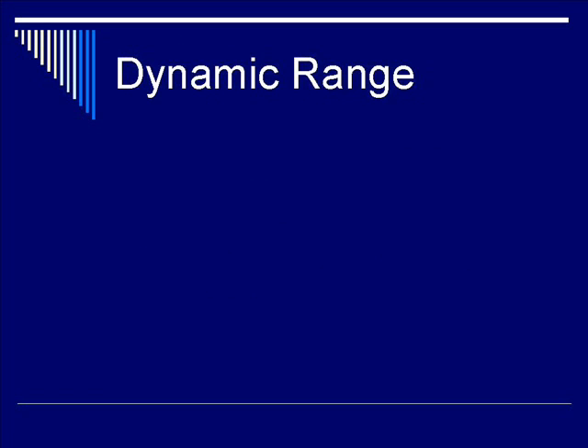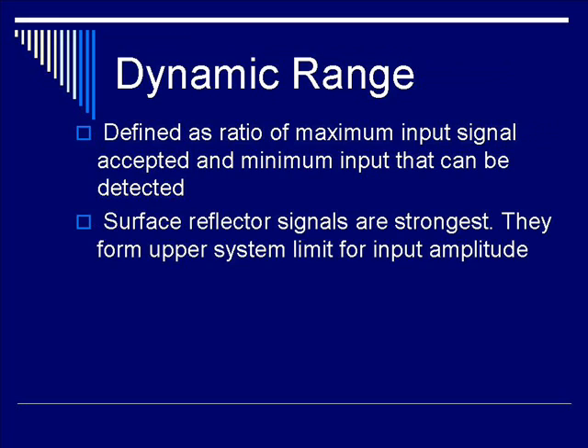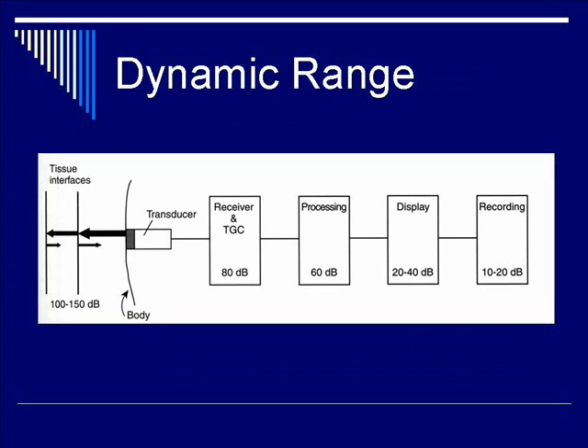The definition of dynamic range is the ratio of the maximum input signal over the minimum input signal that can be detected. Surface reflectors typically give out very strong signals, forming the upper limit for input amplitude. On the other hand, deep reflectors give out very weak signals — sometimes requiring amplification up to 1,000 times just to be detected — and are compromised by noise from the transmission cable as well as the low noise amplifier. In terms of system components, the receiver has a very high dynamic range up to 80 dB, whereas displays and recorders typically have a much lower dynamic range of 20 to 40 dB.